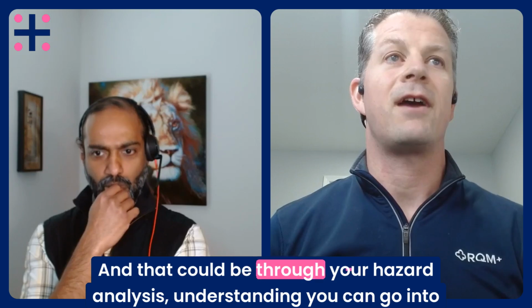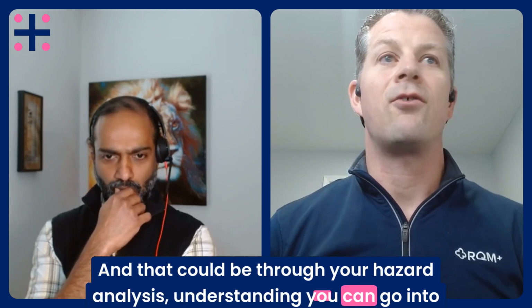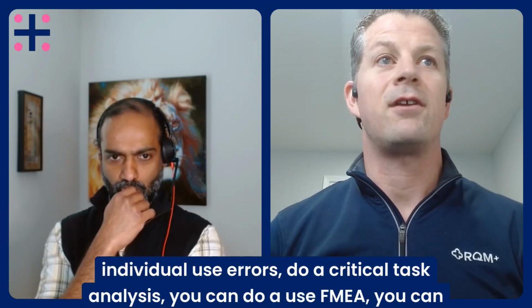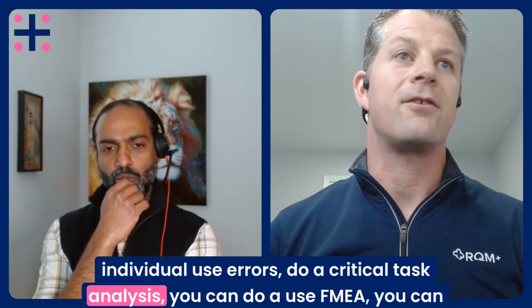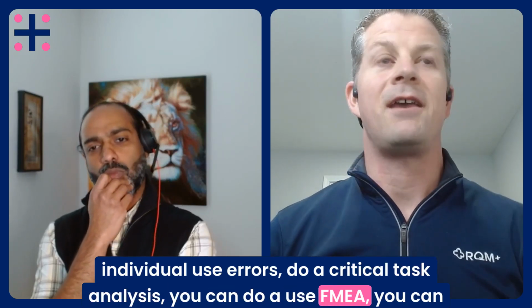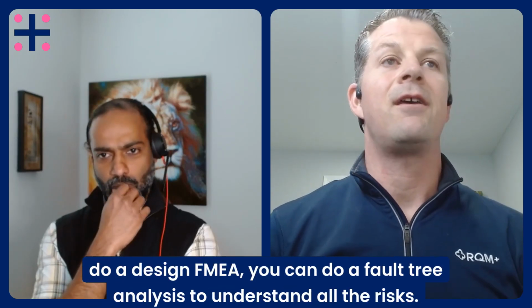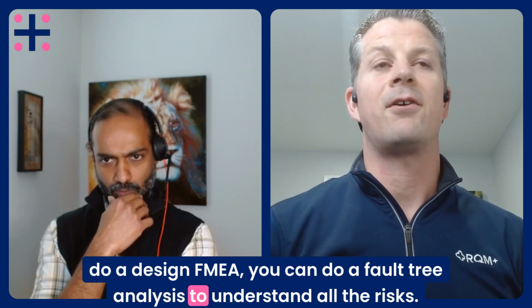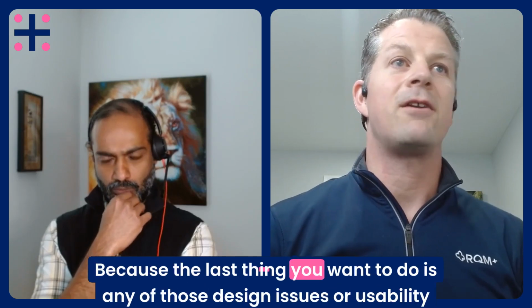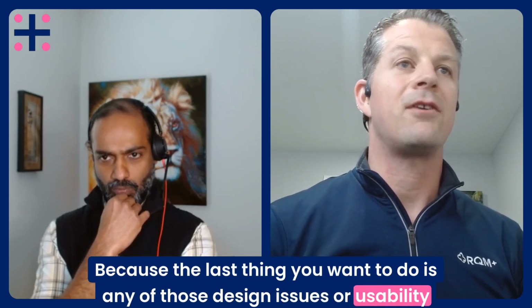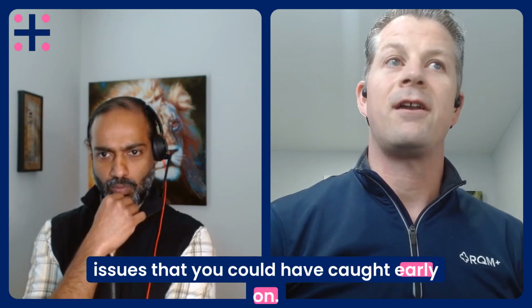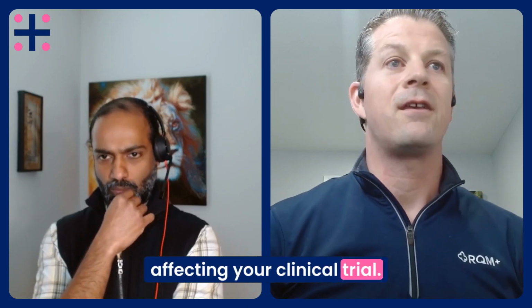And that could be through your hazard analysis, understanding. You can go into individual use errors, do a critical task analysis. You can do a use FMEA, you can do a design FMEA, you can do a fault tree analysis to understand all the risks. Because the last thing you want to do is any of those design issues or usability issues that you could have caught early on affecting your clinical trial.